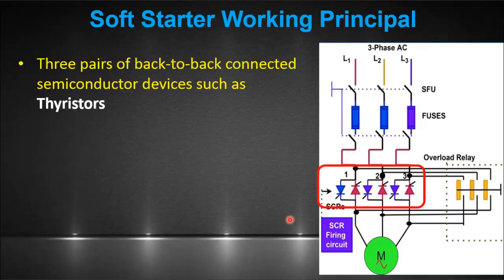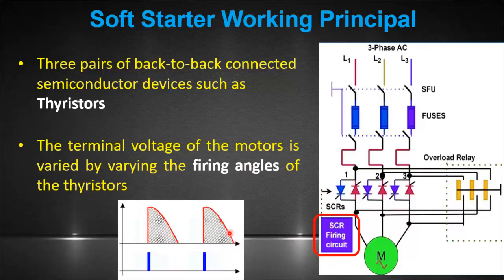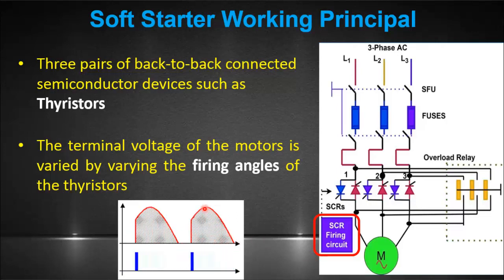Soft Starters utilize three pairs of back-to-back connected semiconductor devices, such as thyristors or silicon-controlled rectifiers (SCRs), as the primary switching elements. These thyristors are switched alternatively to reduce the terminal voltage and inrush current. The terminal voltage of the motors can be controlled by varying the firing angles of the thyristors, as can be seen in the figure.